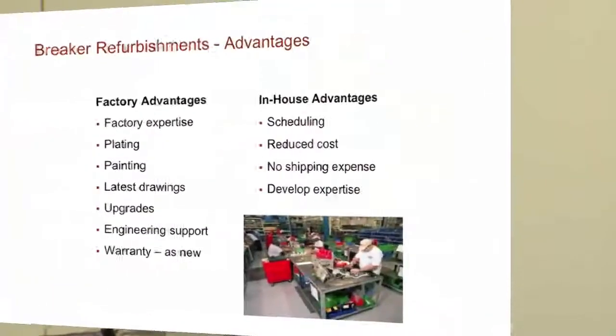And then parts. In many cases, whether we're doing it on low voltage or medium voltage, and this tool can be used for either one, you can standardize on a breaker element. In the low voltage situation, we have an opportunity: I've got a lineup an Eaton Cutler-Hammer over here, I've got a lineup a Square D, and I've got a lineup an ABB. We're able to do a cradle-in-cradle install on those low voltage breakers, and now you've got a standardized element across all three vendors. Now you've reduced the parts inventory, your training, and your procedures down to one standard format.